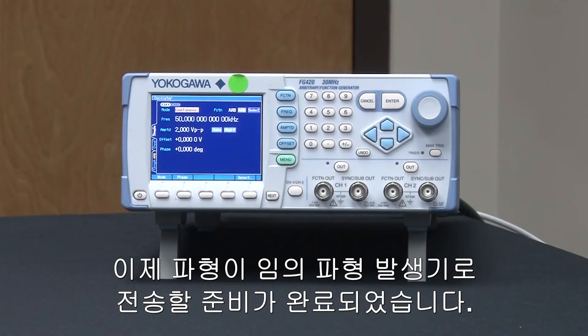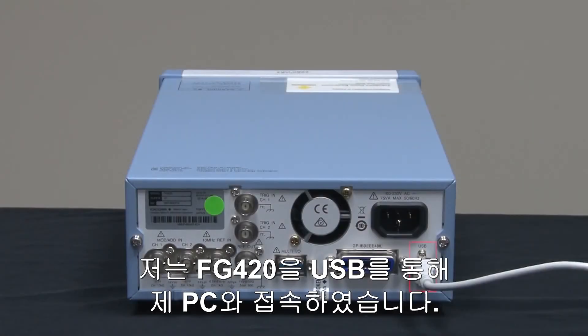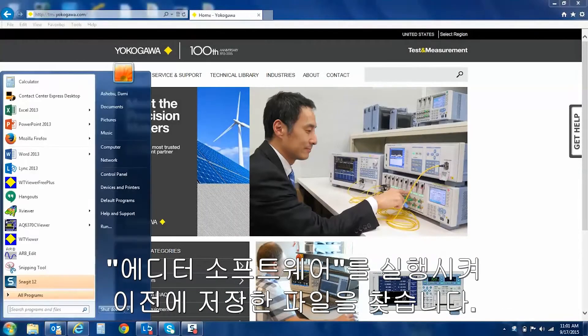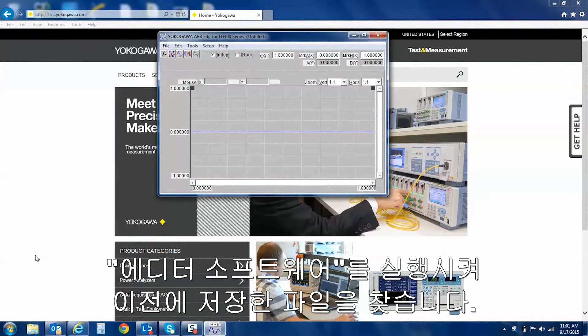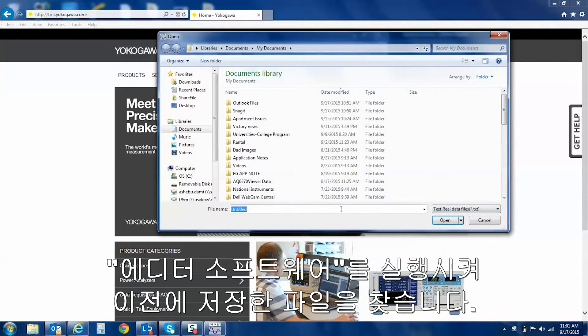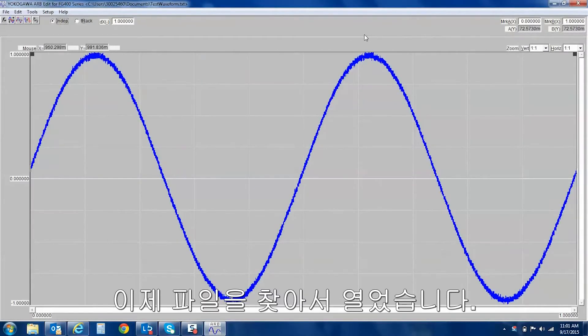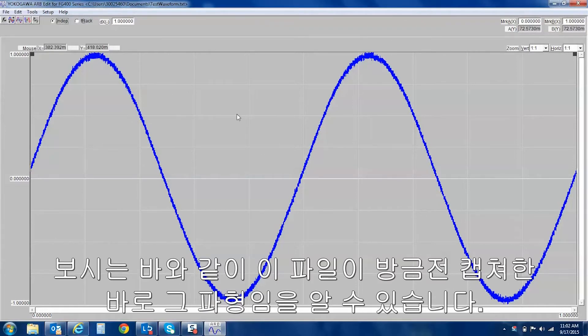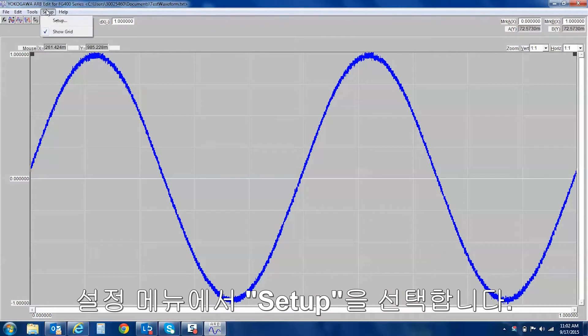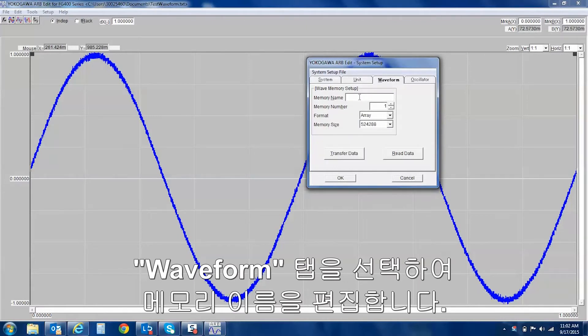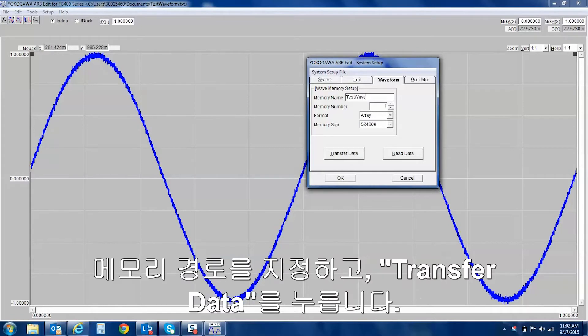The waveform is ready to be transferred to the arbitrary function generator. I have connected my FG420 to my computer through USB. We will open up the arbitrary edit software that comes free with the FG420 and locate the file that was previously saved. Now that the file has been located and opened, you can see that this is indeed the waveform that was previously captured. By simply going into the Setup menu, selecting Setup, selecting the Waveform tab, adding a memory name, selecting a memory location, and simply pressing Transfer Data.